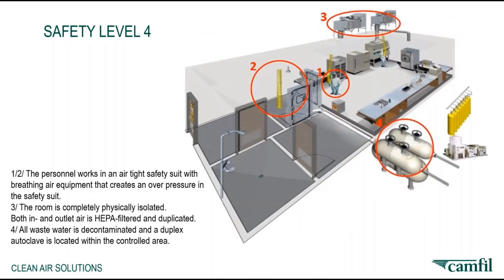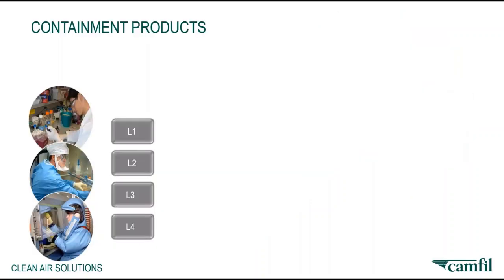Safety level 4 is the highest safety level. Personnel work in an airtight safety suit with breathing air equipment that creates an over pressure inside the suit. The room is completely physically isolated. Both inlet and outlet air are HEPA filtered and duplicated. All wastewater is decontaminated, and a duplex autoclave is located within the controlled area. Working alone is not allowed.